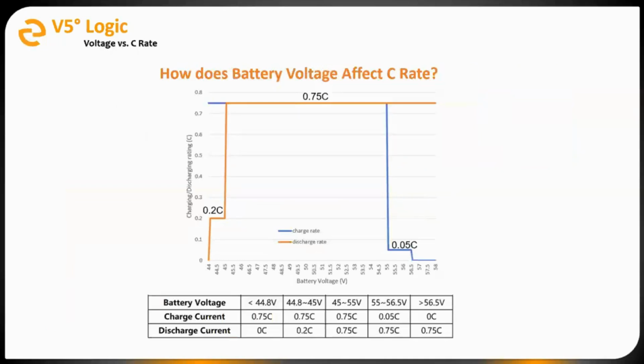So a couple more things on the BMS. I'm going to go through a couple slides that just show how different parameters affect battery operation, specifically our charge and discharge rate. So this first one, we're going to look at battery voltage versus charge rate, and how it affects the charge rate. We don't have to focus too much on the details here, but just the main themes or takeaways from this information. I'll point out that in this range, 45 to 55 volts DC, everything's normal. So as I mentioned earlier, the V5 battery is 0.75 C charge and discharge rate, that's 75 amps per battery. So the percentage here is in relation to 100 amp hours.